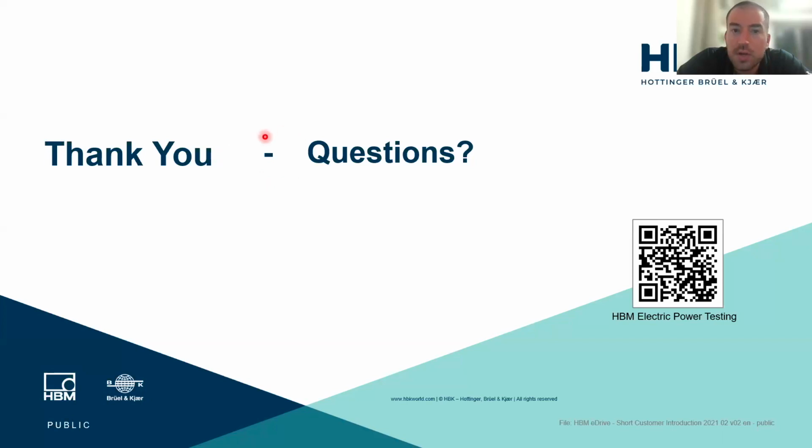So I got a question from Constantine. He asked it twice, so I'll try to answer. Does it make sense to also use ferrites for the sensor wires? Ferrites can certainly make sense, especially on digital signals. It doesn't hurt anything. It's basically helping eliminate some of that noise. You're introducing loops typically to do it. So I would say really focus on the cable layout for power carriers. For digital signals, life's a little different.